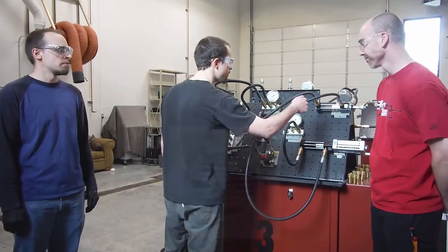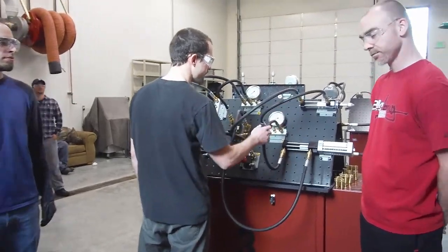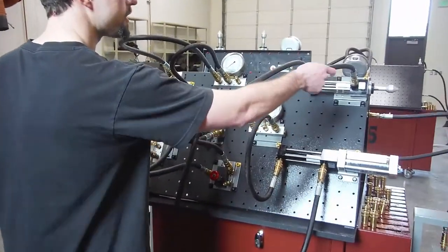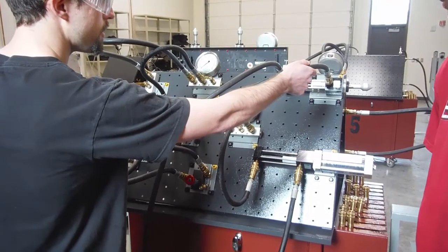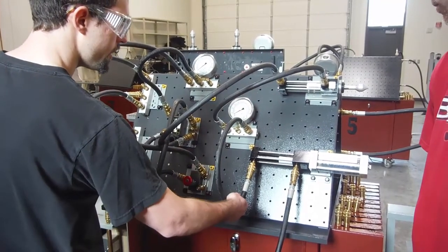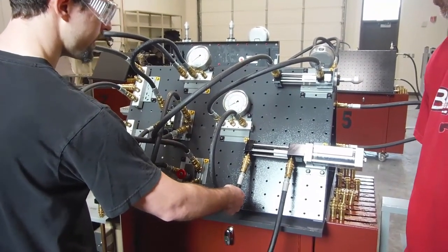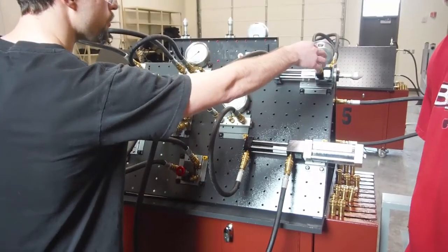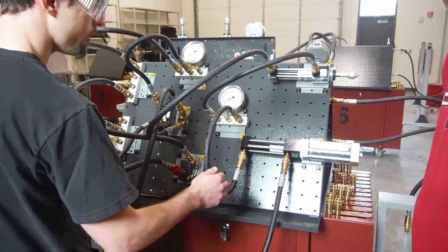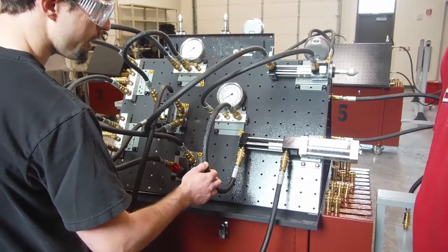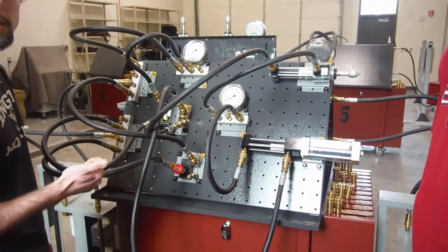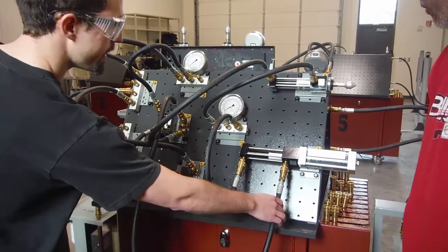So with this circuit, we're going to have two hydraulic cylinders in series with each other. We're going to have a fixed volume of fluid moving in through the outflow of this cylinder into the inflow of this cylinder. So with the different areas of the rod end and the cap end, it's going to result in two things that we're going to focus on, and that is pressure and force intensification and then simultaneous movement with the rods.